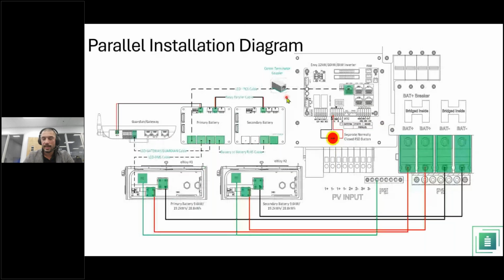You basically do the same thing when doing parallel systems with eWays. From here, you take the battery to battery RJ45 cable that's already included to parallel the systems. The terminator that was initially here now goes here to terminate that communication, and then you have your relay parallel cable as described previously.